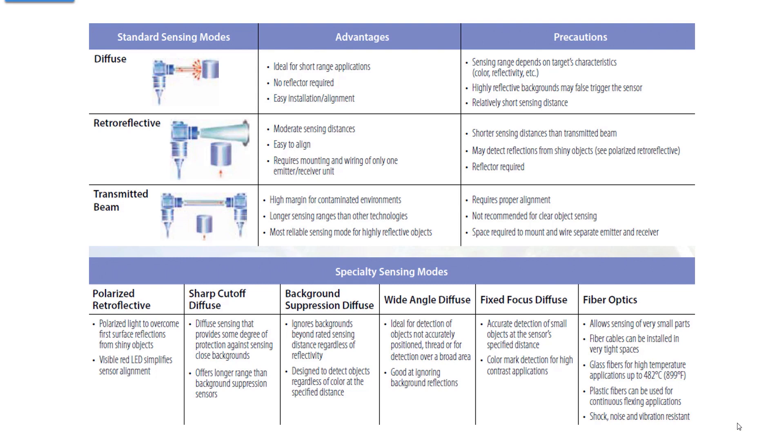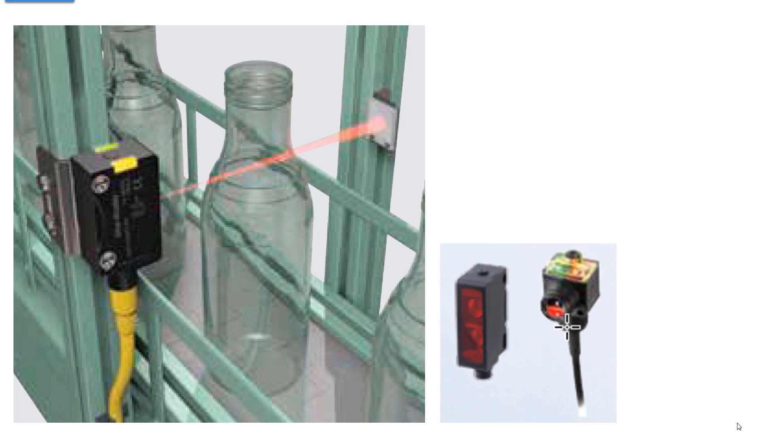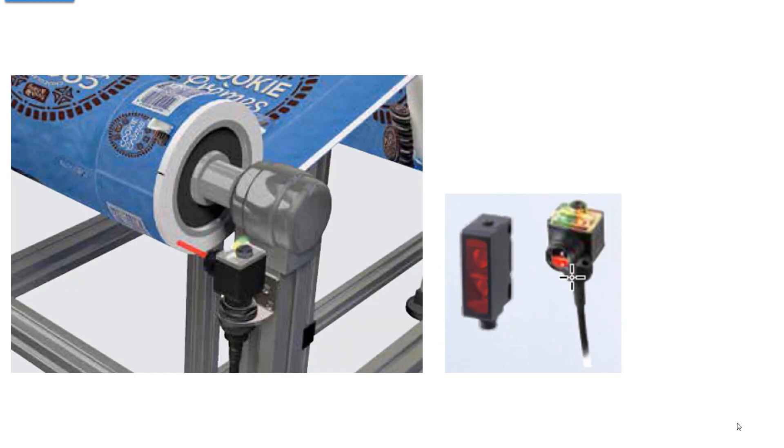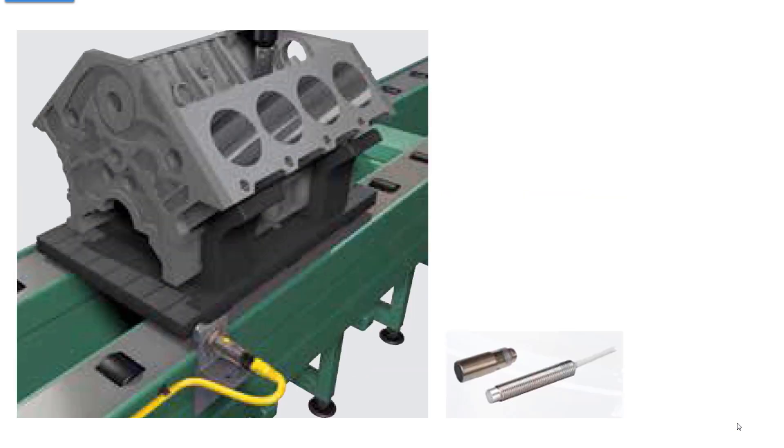Now here a sensor with a reflector is sensing empty bottles on a line. Most of these sensors have two LEDs - one to show that there's power on it and the other to show whether it's tripped or not. That helps you when you're adjusting the sensitivity. Here's a diffuse photo eye looking at the edge of a roll of either paper or plastic. When the roll gets too low it no longer sees it and says you need to replace it.